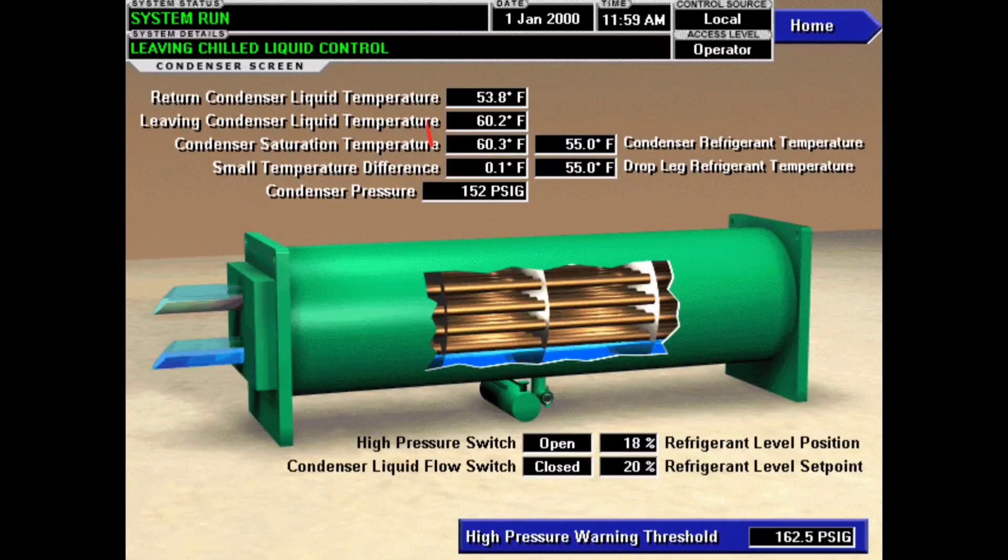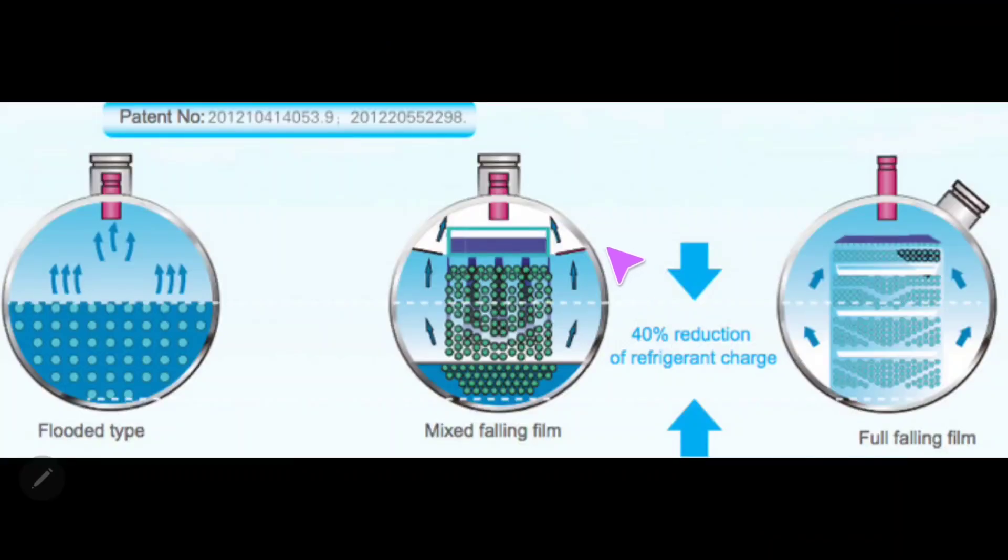What they did for us here is they actually put the calculation right here. These two numbers is what's being calculated: it's the leaving condenser liquid temperature and the condenser saturation temperature subtracted from each other, and that difference gives you your approach value. Small temperature difference is just how York refers to it, but inevitably it means approach.